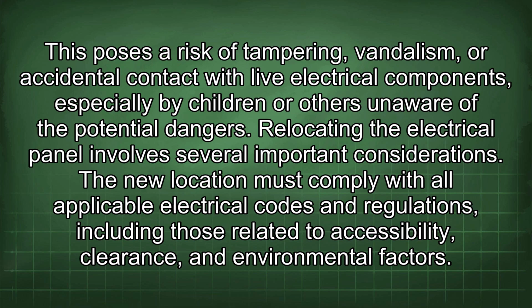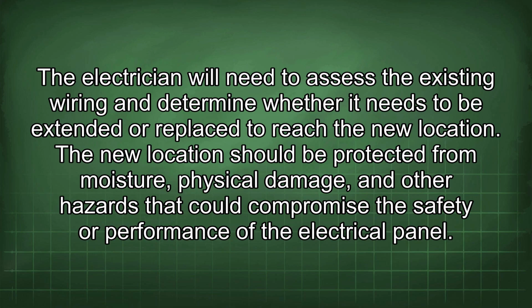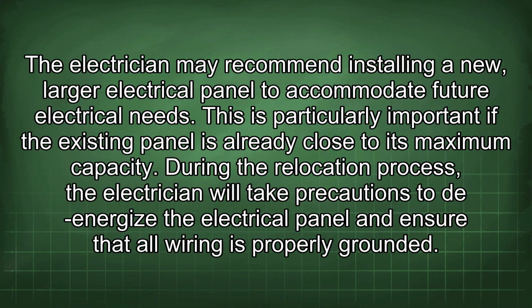Relocating the electrical panel involves several important considerations. The new location must comply with all applicable electrical codes and regulations, including those related to accessibility, clearance, and environmental factors. The electrician will need to assess the existing wiring and determine whether it needs to be extended or replaced to reach the new location. The new location should be protected from moisture, physical damage, and other hazards that could compromise the safety or performance of the electrical panel. The electrician may recommend installing a new, larger electrical panel to accommodate future electrical needs. This is particularly important if the existing panel is already close to its maximum capacity.